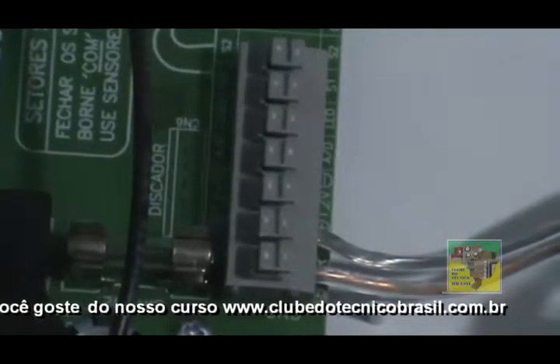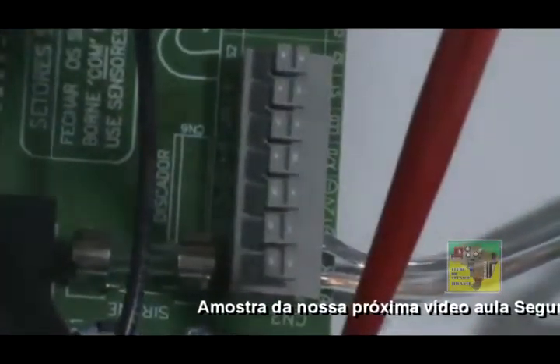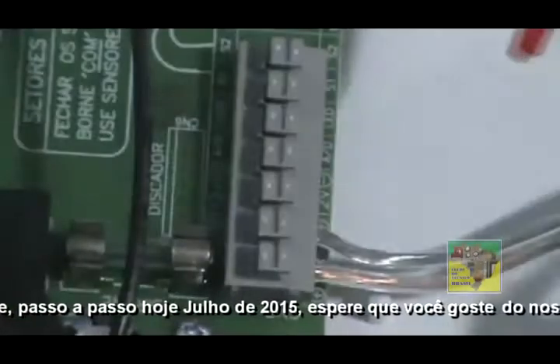Faça isso, pessoal. Uma boa conexão, uma boa verificação, você não tem problema. Se houver algum erro na central, você vai saber que os seus cabos estão bem conectados e as emendas estão bem perfeitas. Você verifica todos os cabinhos — esse aqui já estava, já vem do transformador para cá, para a nossa placa. Essa é a dica.